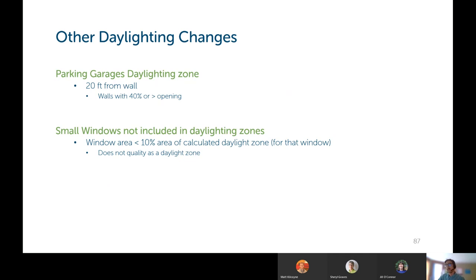Other daylighting changes are that parking garages now have included daylighting zones. Any fixture that is 20 feet from a wall that has 40% or more openings would need to follow daylighting requirements. And if you have a really small window, where the size of the window is less than 10% of the calculated daylight zone for that window, then you would not use that in the daylighting zone. It would not qualify as a daylighting zone. So if you have a really tiny window, you might be able to calculate a large projection of daylight zone, but the code wants to not have that happen.